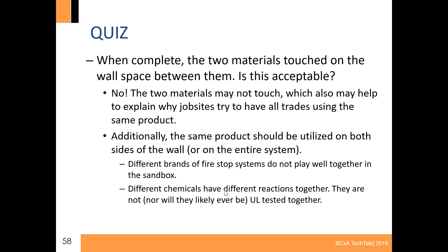So, is this a life safety code issue? It is, because IBC requires that all penetrations to rated assemblies must use an approved and tested system—tested meaning UL tested. Going to the simple pieces, mixing fire-stopping products from different manufacturers is definitely a big no-no.